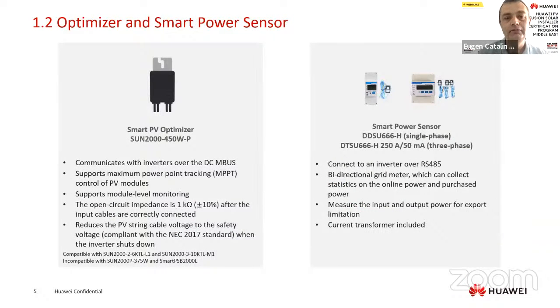Optimizer, the new optimizer, SUN2000-450W. Communicates over DC power line. The communication between optimizer and inverter should be made through DC cable. Support maximum power point tracking. Support module level monitoring when we use optimizer, of course. We don't have voltage when we use optimizer, and we need to measure the impedance, that should be 1 kilo ohm per optimizer, per panel with optimizer, plus minus 10%, and reduce the PV string cable voltage to the safety voltage according to the standard NEC 2017 when the inverter shuts down. It's a rapid shutdown function.